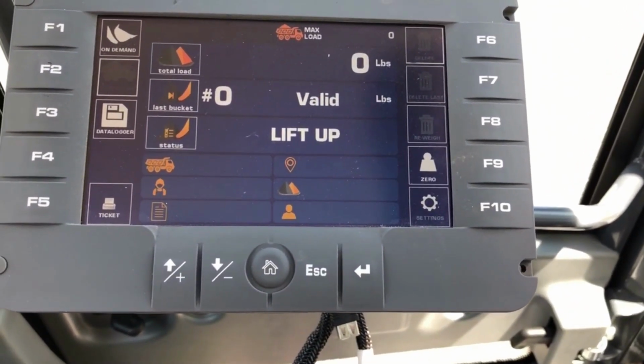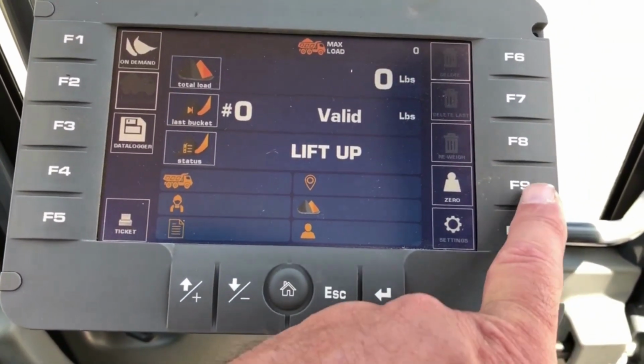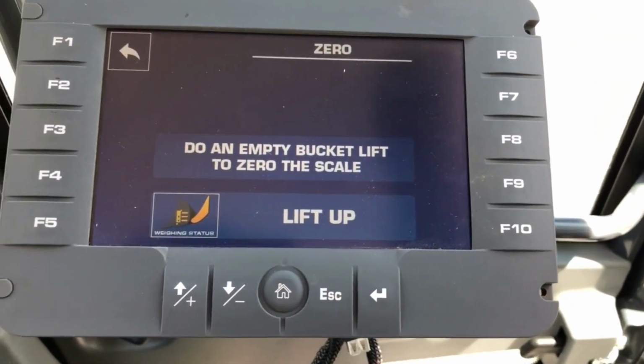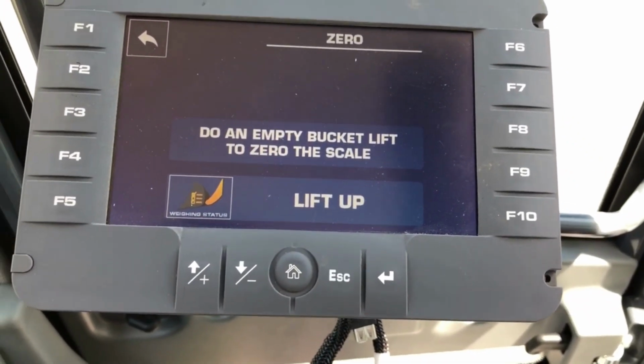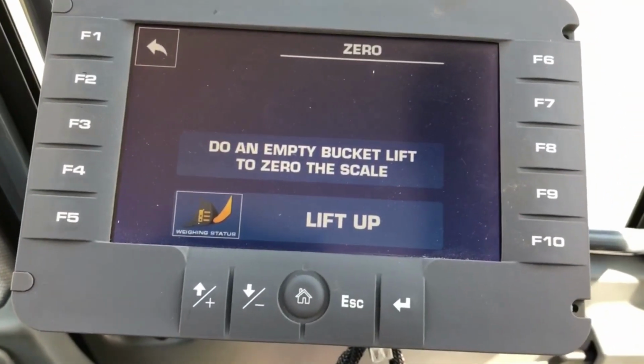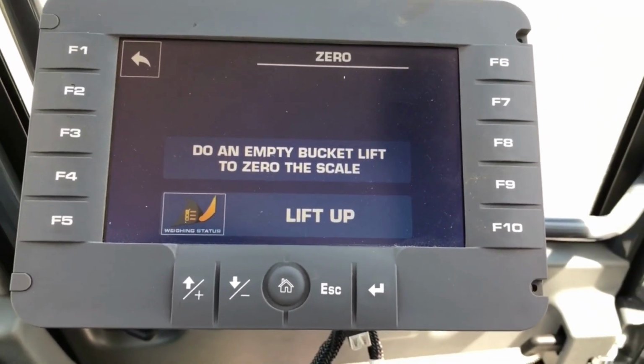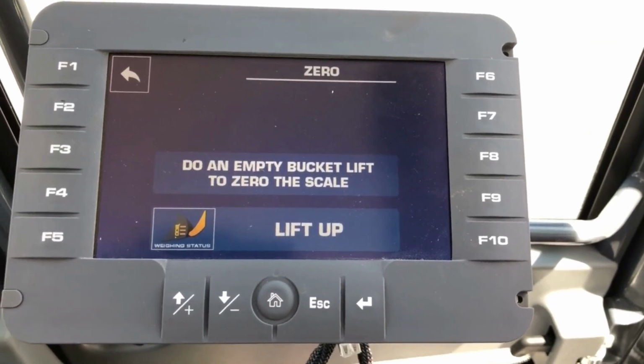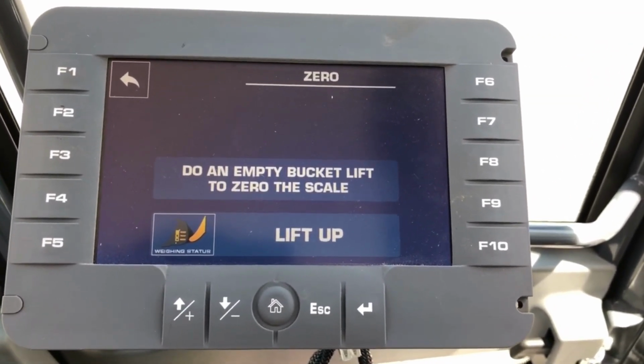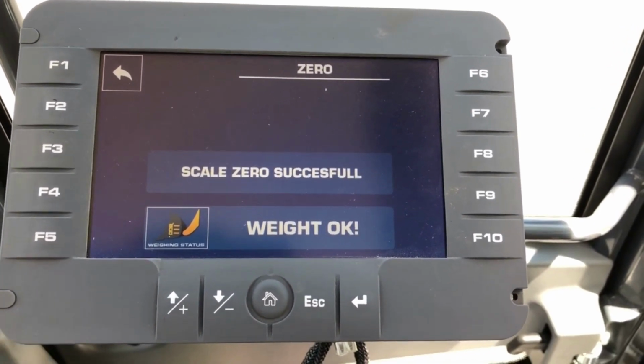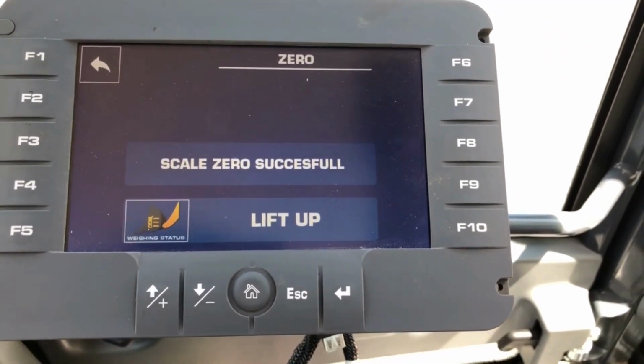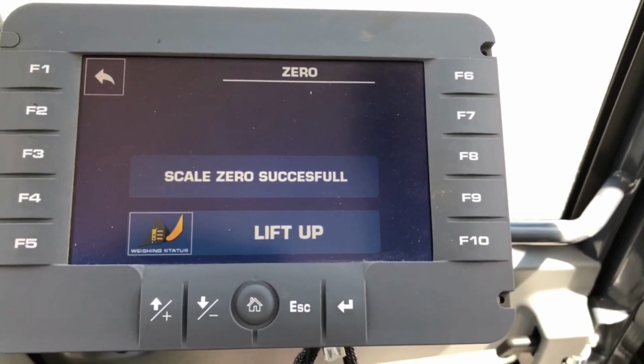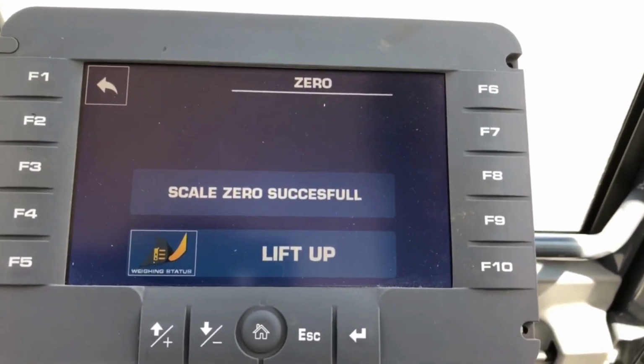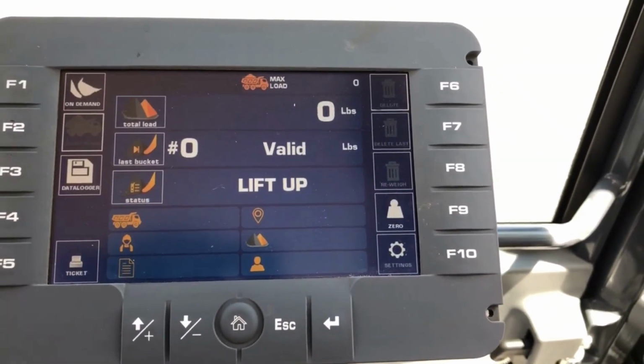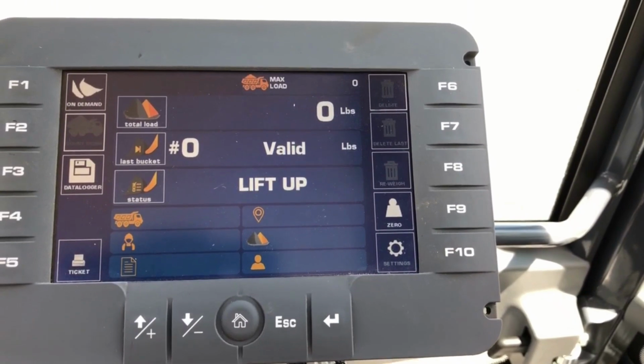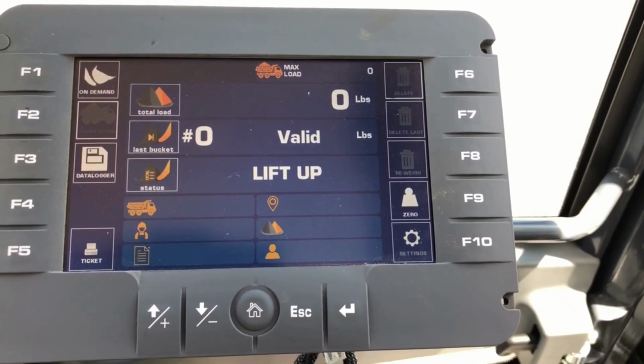The next thing we would recommend doing is zeroing the bucket. So we want you to hit F9. It's asking you to just please do an empty lift. So my bucket is empty still there, so I'm going to go ahead and do a lift. And it says that it was successful. So we come back down, and then I'm going to hit F1. Now the scale is calibrated and zeroed and ready to weigh your material.